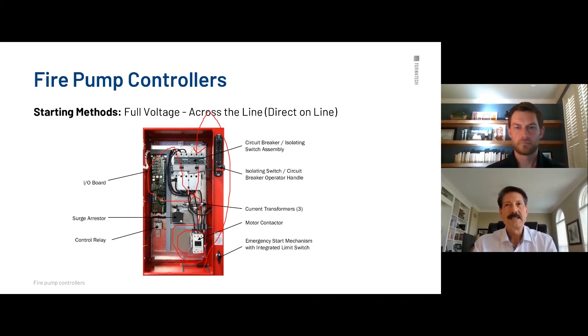So I mentioned before, it's quite easy to size an electric fire pump controller. All we need as a manufacturer is the horsepower and the voltage and all the work and calculations of all the components within this enclosure are done by us. I need the HP and I need the full load or the HP and the voltage. Now on higher horsepowers, we might get into the fringe area where we might say, hey, we need to see the motor data sheet because we want to see what the amperage draw is. Again, this is typically you're talking a direct online, you know, six times full load amperage.